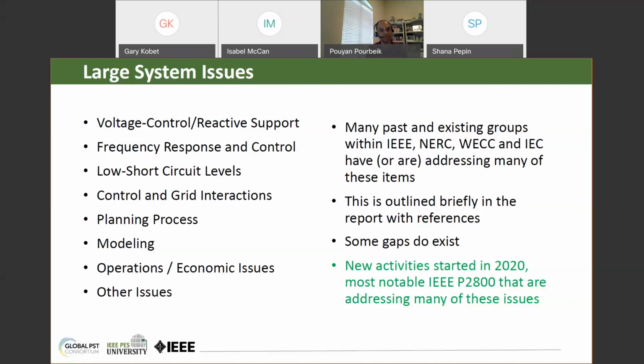So we discussed in the report, obviously, things like voltage control, reactive support that you would expect from inverter-based generation, frequency response and frequency control. What are some of the issues related to low short circuit levels on the system, control and grid interactions between the controls of the power electronics and the grid, like in the case you have series compensation or if you have other devices close by. What are some of the issues around planning processes, around modeling of these devices, operational economic issues, and honestly, in that regard, we basically say in the report that economics is outside the scope of what we discuss here. This is a very technical report, but just to state that. And then some basic other issues were discussed as well.